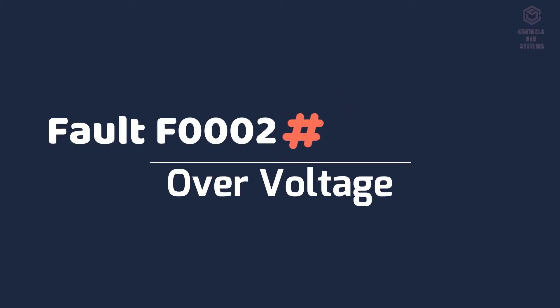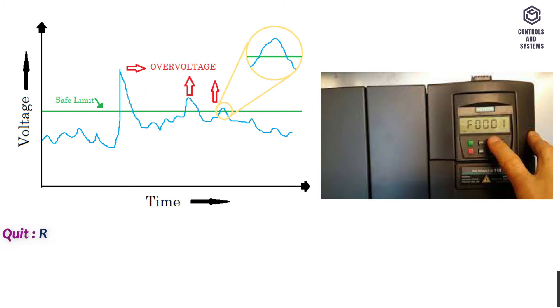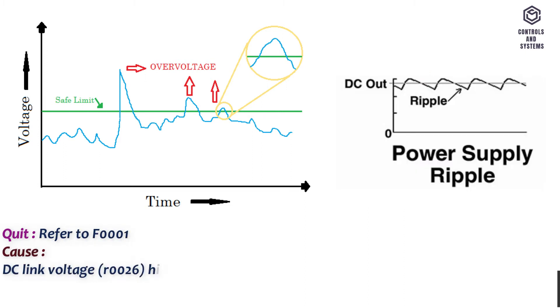Fault F0002 overvoltage. Quit: Refer to F0001. Cause: DC link voltage R0026 higher than the overvoltage threshold. Refer to parameter R0026. Ground fault.